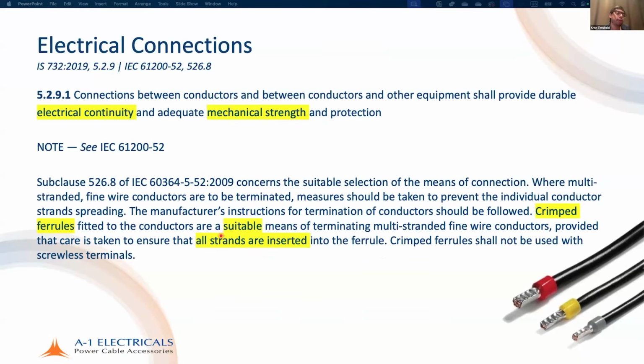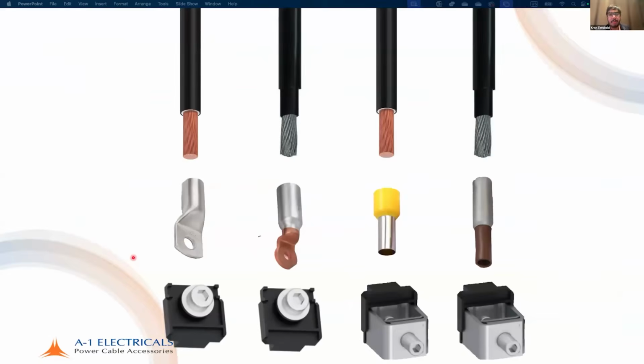The crimped ferrules should not be used with screwless terminals. For some examples, apart from box terminals, nut keeper terminals are very common, for example, on MCCBs and contactors, on spreader links, etc. So you have a copper conductor entering a terminal lug, which is a ring type on a nut keeper. We have an aluminum conductor entering a terminal lug, which is bimetallic, to ensure that there is no corrosion. I'll explain that in a moment. Copper conductor entering a bootlace ferrule in a box terminal, aluminum conductor entering a similar lug in a box terminal.